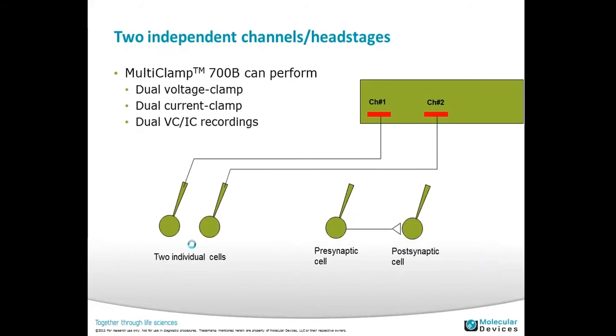Now I like 700B because it has two independent channels. They come with two head stages, so with 700B you can perform double patch for voltage clamp, double patch for current clamp, or use one for voltage clamp and the other for current clamp. You can patch two individual cells just like this, connecting a head stage to one cell and another head stage to another cell.